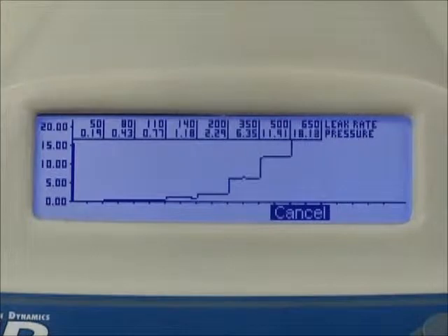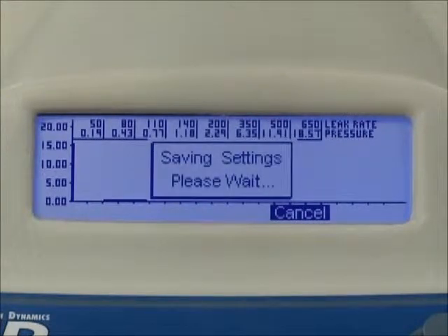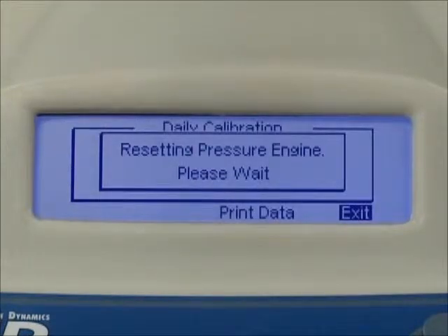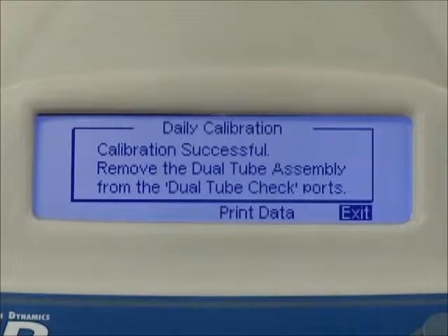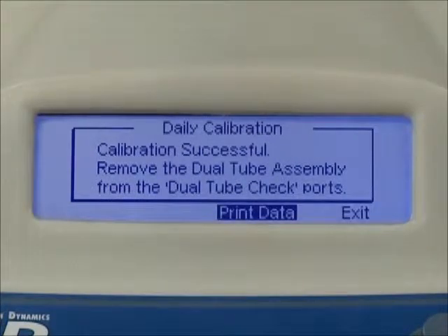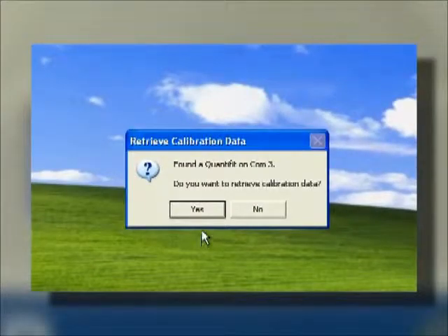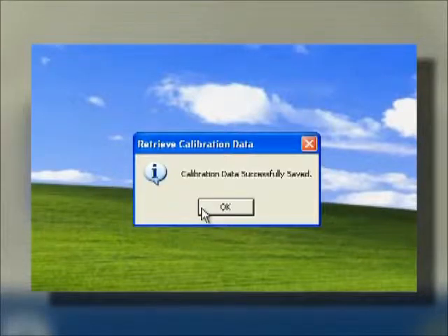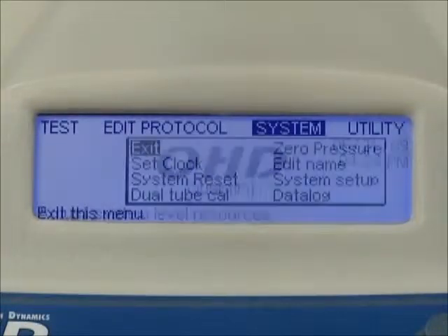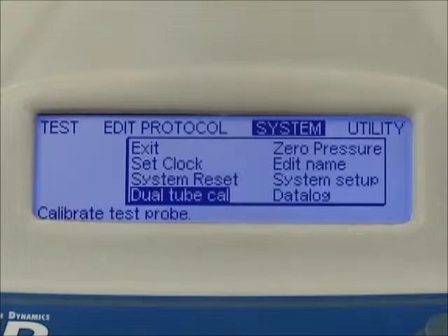When the calibration is complete, the results are saved into the internal memory of the Quantifit. The Quantifit stores only the most recent calibration. To print a copy of the calibration, select Print. If you are running the FitTrack software, you can save the calibration data in the computer database. We'll discuss that process later in this presentation. If for any reason you wish to do a second daily calibration, you can go to the Dual Tube Cal under the System menu and repeat this procedure.